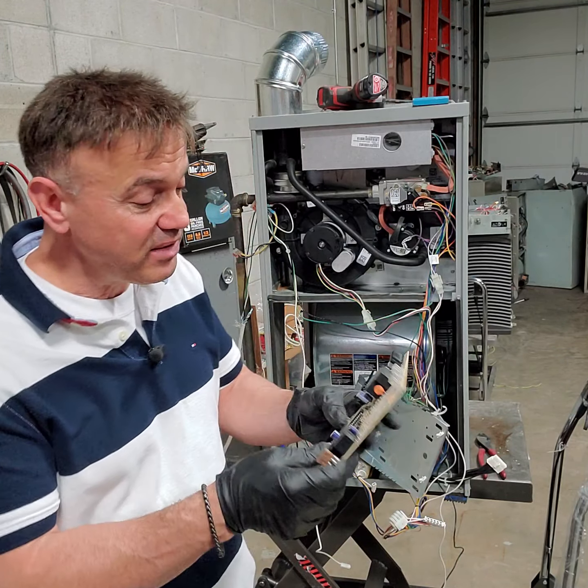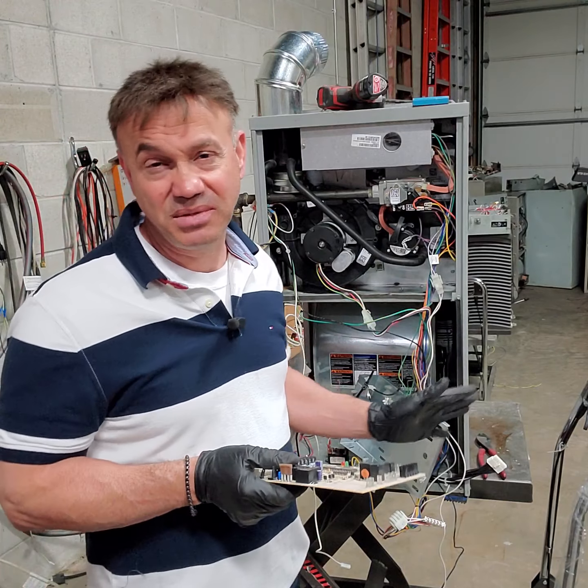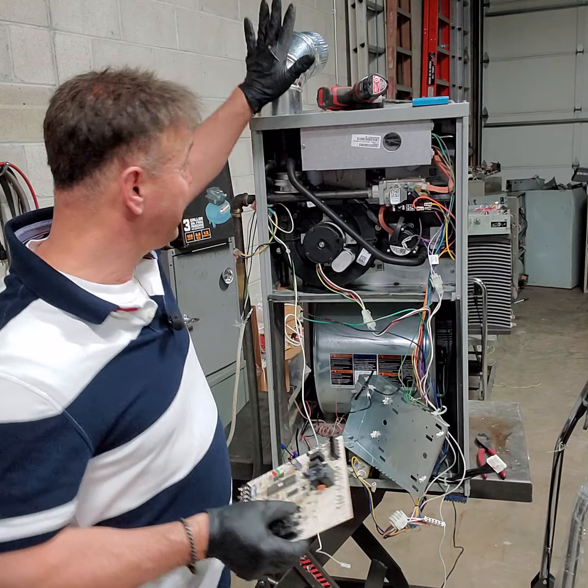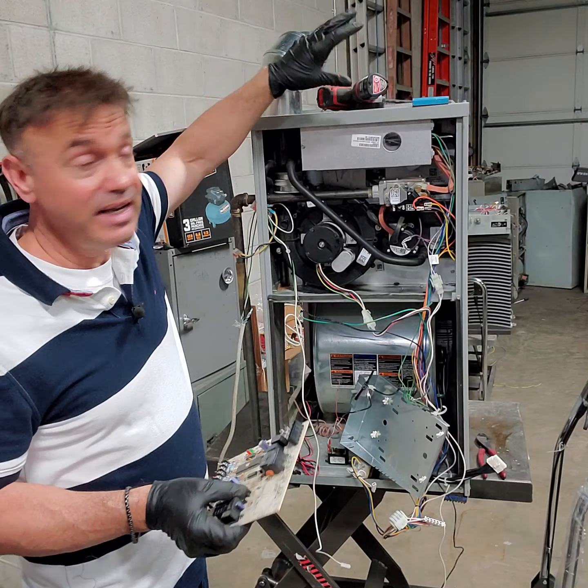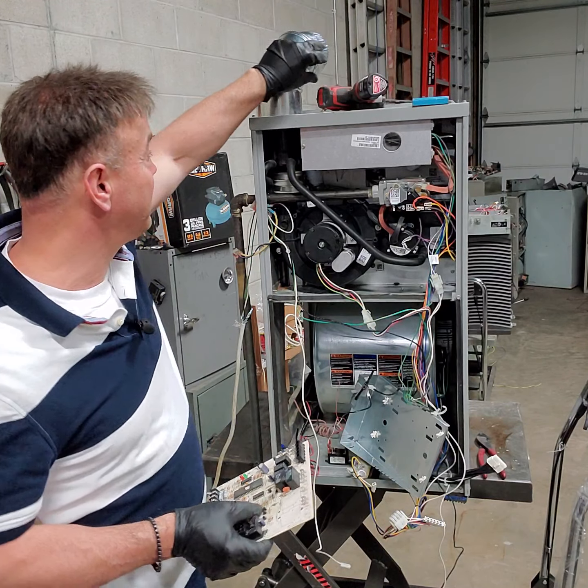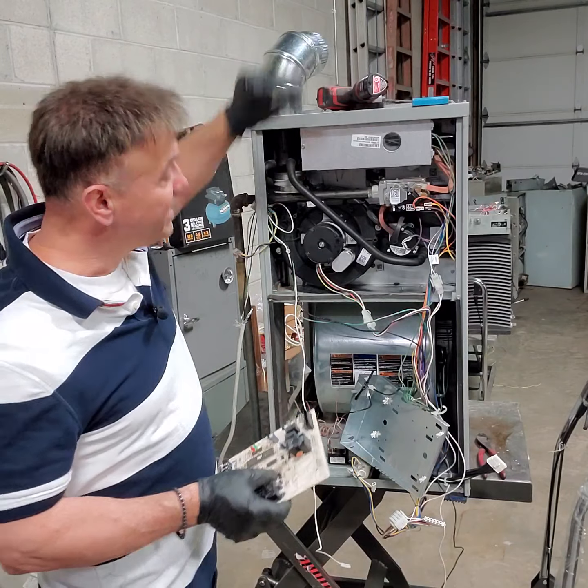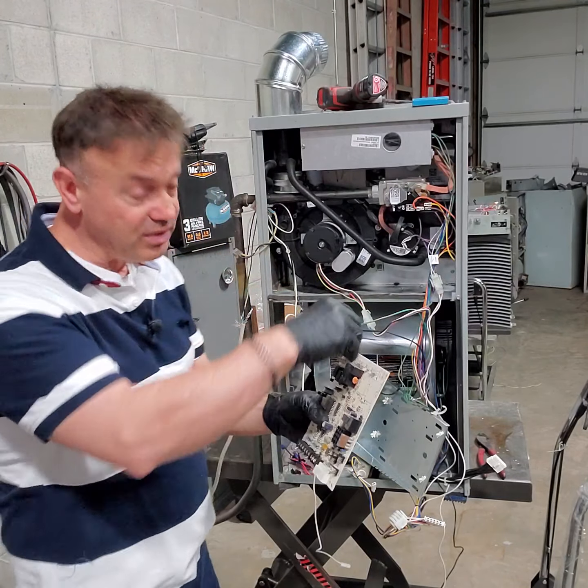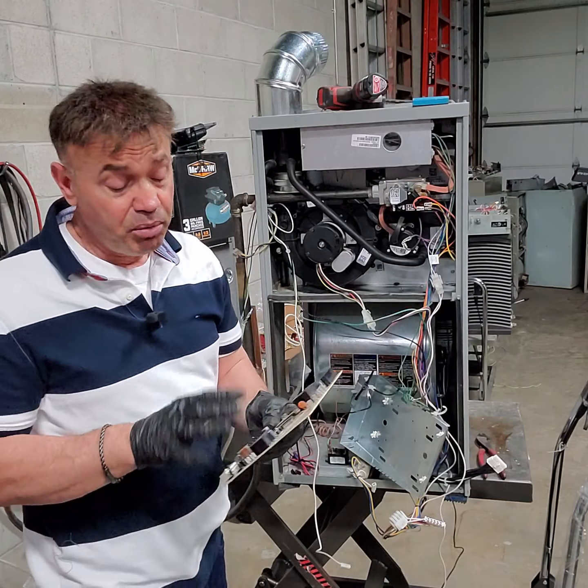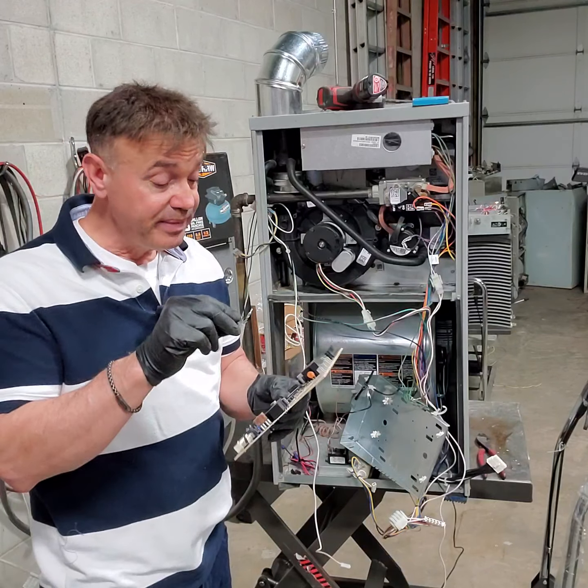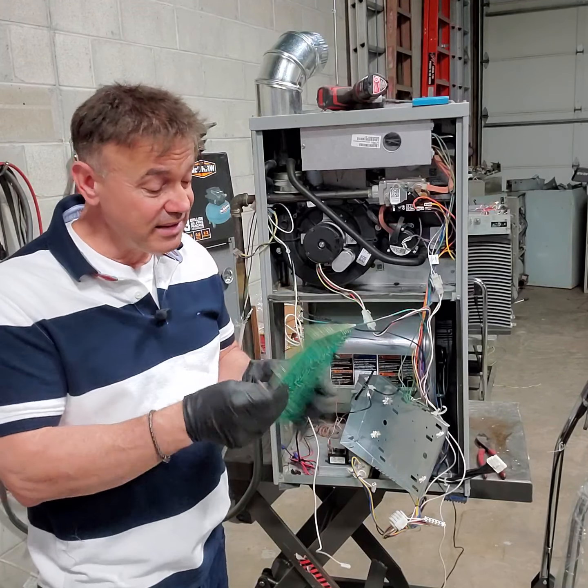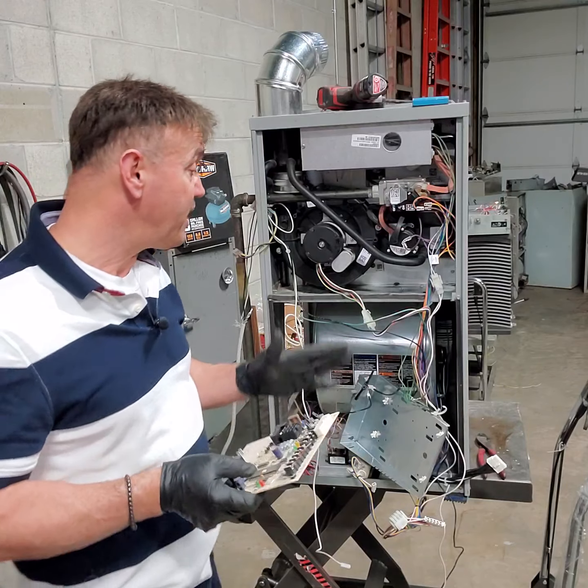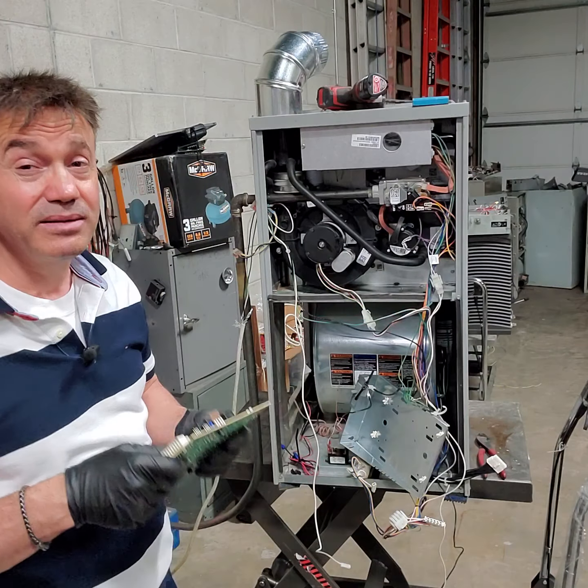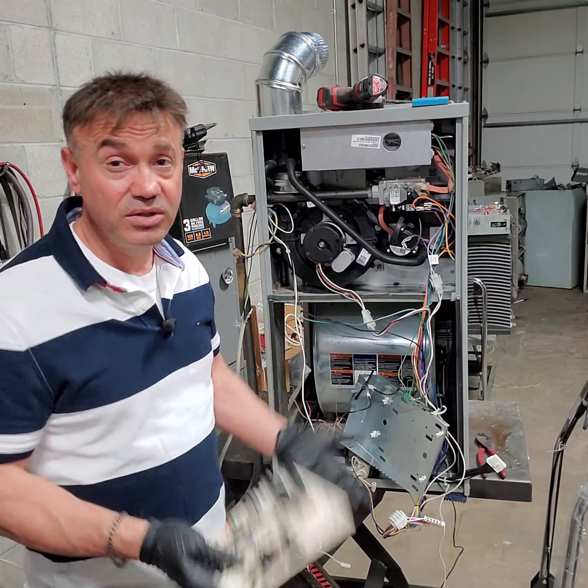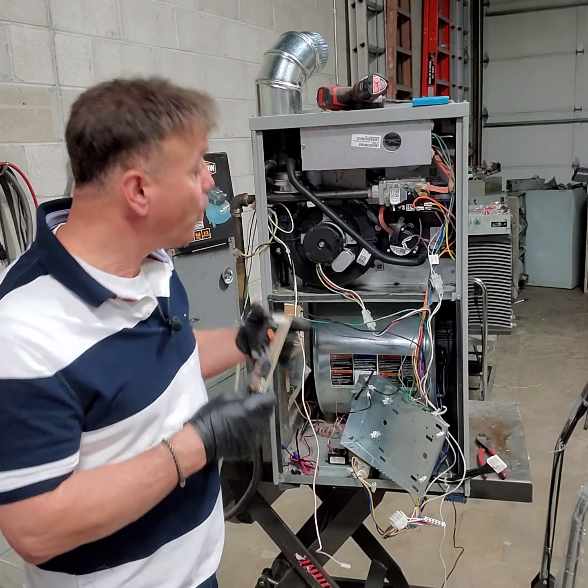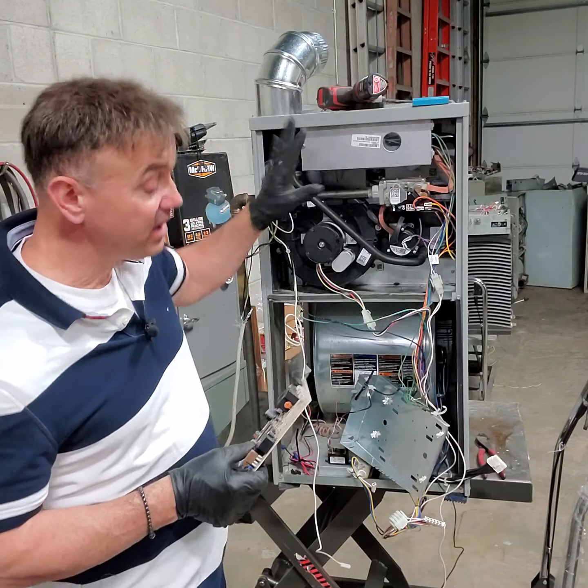The only time this goes bad is when somebody messes with it without knowing what they're doing, or from water. When the AC coil is leaking, there's an outlet - I don't have it here, but you know what I mean - and that leaks through the furnace and reaches the control board. The board can resist water to some degree, but if the water is constant, it's going to start frying things. So the only time a control board goes bad is when people mess with it without knowing what they're doing, or from leakage.